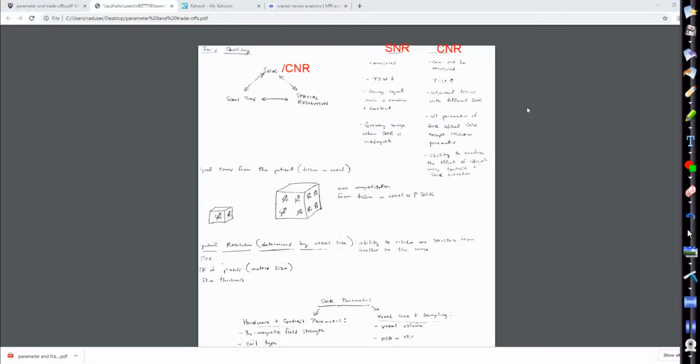Okay? So signal to noise, if you look at your scanner, usually you'll have 1.00, meaning you have 100% signal coming from your patient. And you want it to maintain around that 100%. You want good signal for your images. So that's something that can actually be measured. So as we adjust these parameters, our signal, you're going to notice, goes up and down. But remember, our radiologist wants really good signal because we don't want a really grainy image.